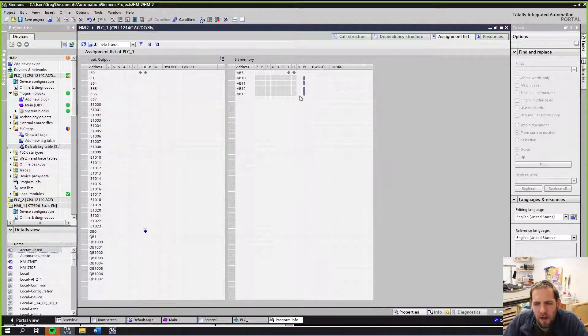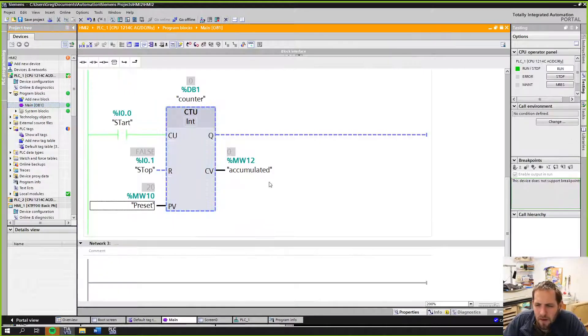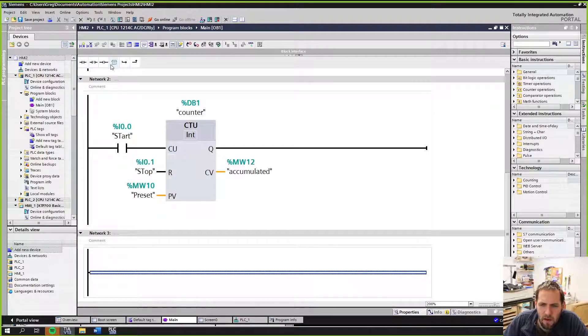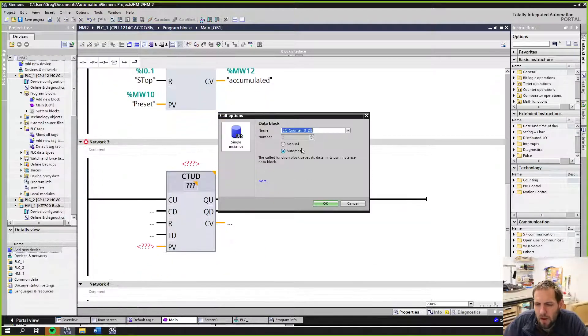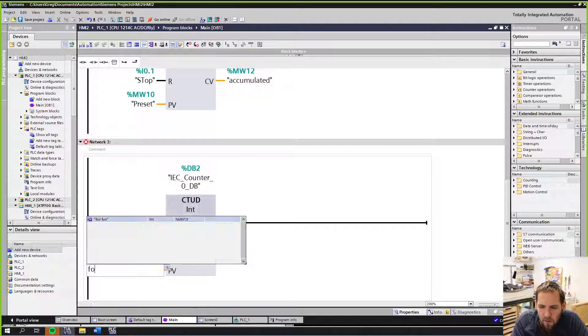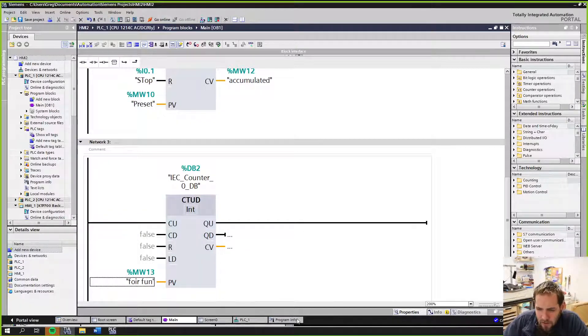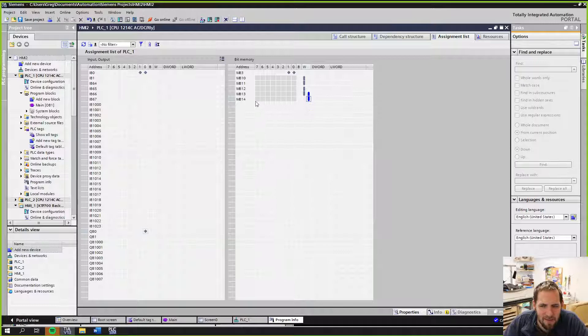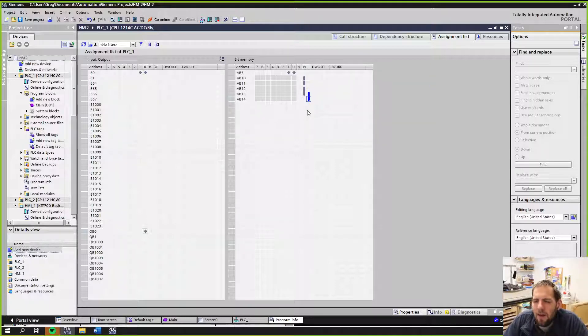If I come back to my program, 'for fun' isn't showing here yet. Let's go offline and put in a new count up/down counter, and we'll call this the fourth one. Now I've used it. If I go back to program information, you can see I've got overlap here. Half of this is coming from address 13 and half from 14. It needs 16 bits for that word — a word is 16 bits.